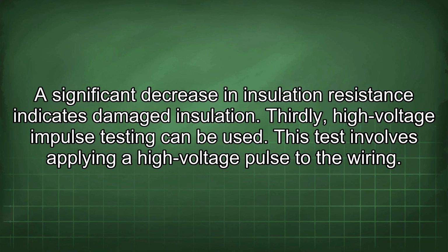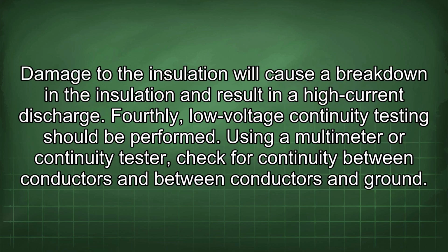Thirdly, high voltage impulse testing can be used. This test involves applying a high voltage pulse to the wiring. Damage to the insulation will cause a breakdown in the insulation and result in a high current discharge.